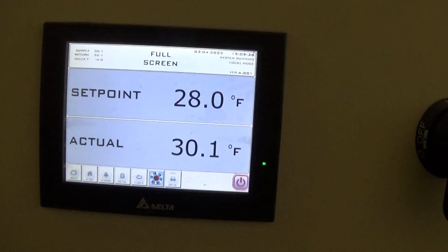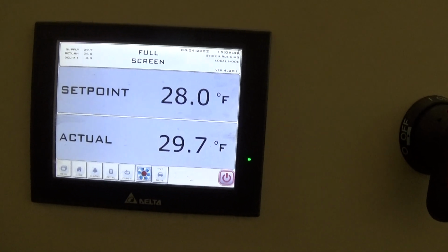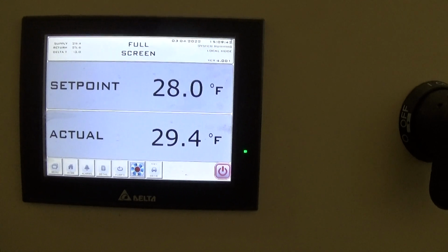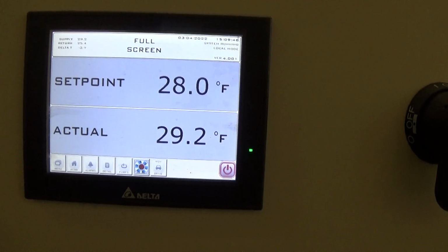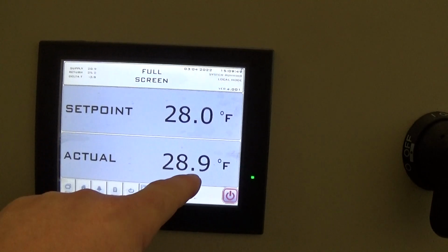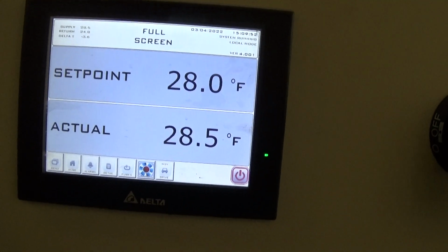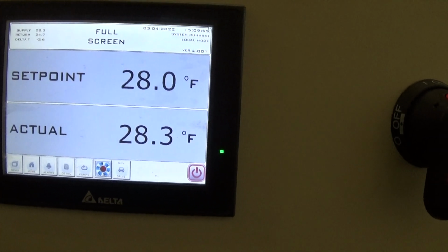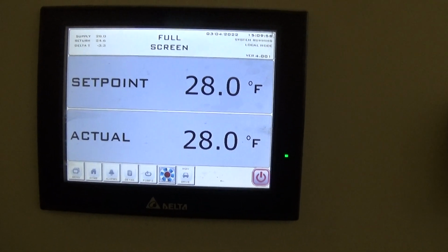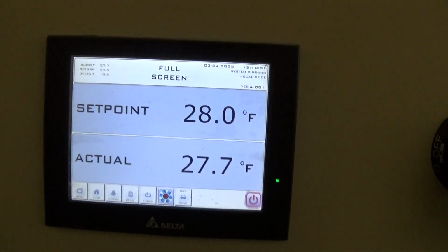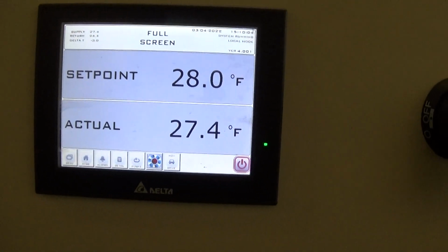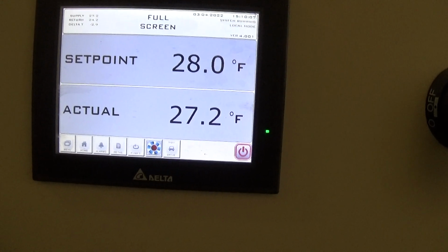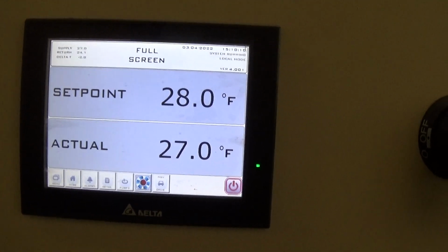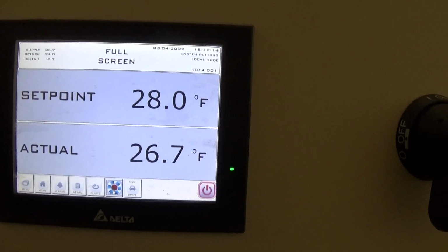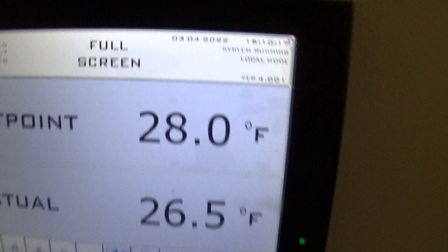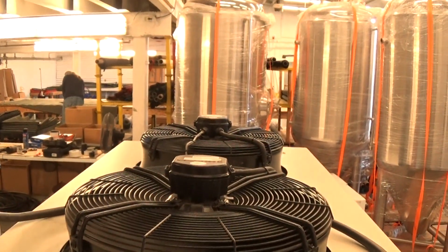Full. Oh, that was pretty quick. So you can hear the RPMs ramping down again. So set point 28. This rate of cooling will probably slow as we get closer to the set point, and we should go a couple degrees or 2 like I showed you in that prior screen below set point. We've been running this thing, by the way, for a week or so, adjusted a few things, but again, a real impressive piece of machinery. And the fans also that are running up above here, these are also variable speed.